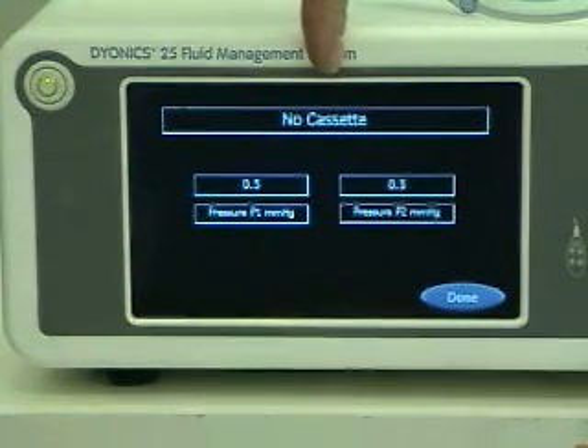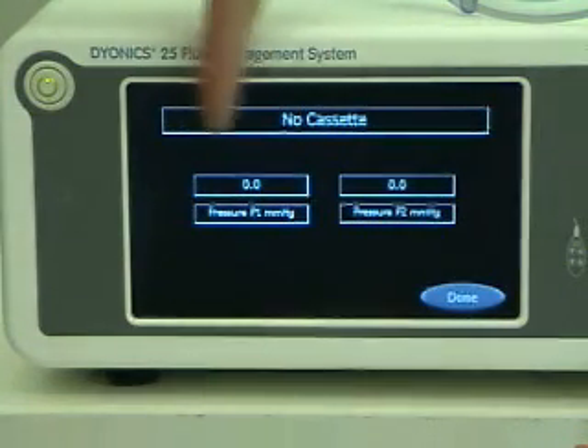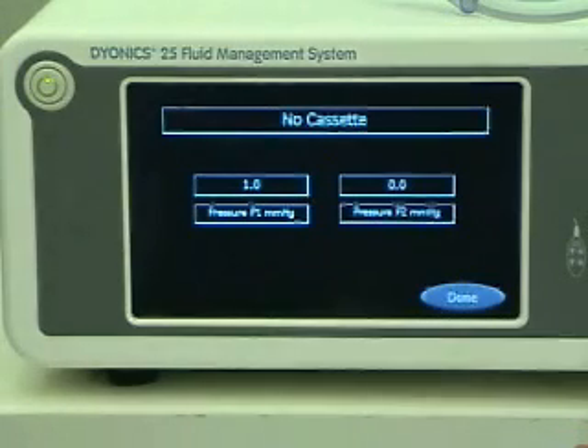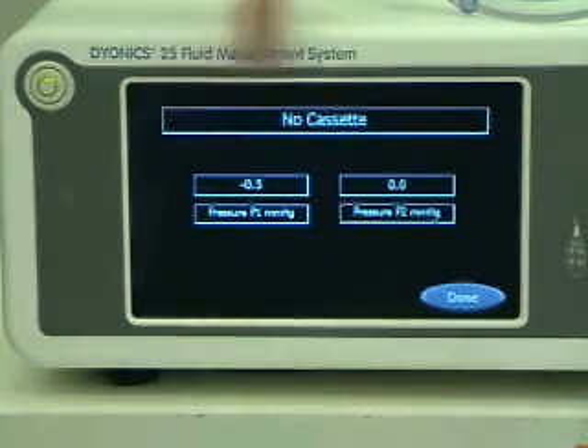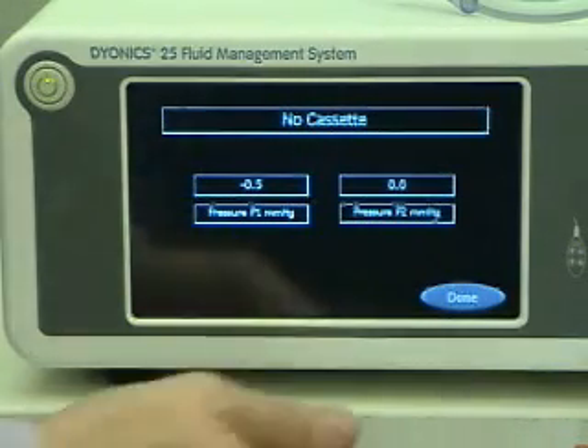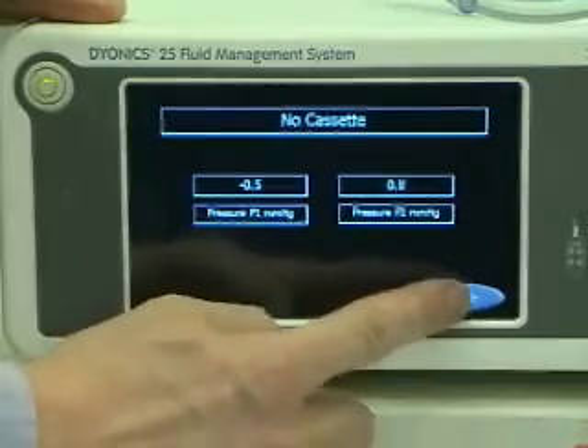It's telling you there's no cassette inserted, and then giving you the actual pressure readings of each of the two transducers. And the offset is such that if either of those two numbers is less than plus or minus 10 from 0, then the transducers are in calibration. So that's the first test that you can make. So by checking those two numbers are both less than plus or minus 10, you know that the transducers are okay. You press the done button.